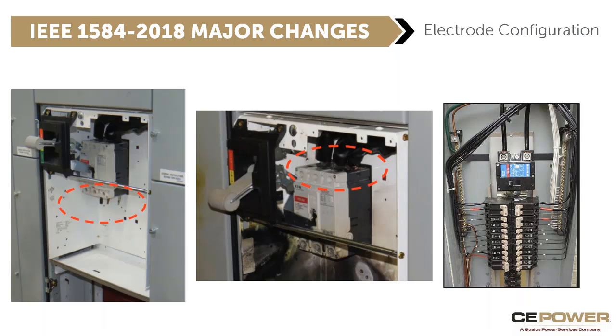If you have a fault in the region shown in the picture in the middle, well, that's VCBB. And so we've got the same enclosure, and depending on where a fault occurs, we have 2 different types of electrode configurations that we need to consider. So what do we do? This is the hard part of considering these correctly.